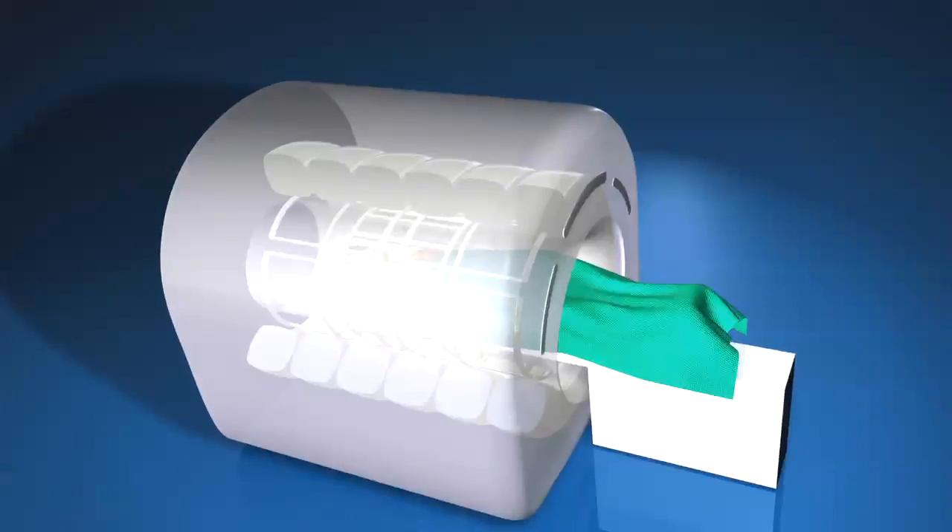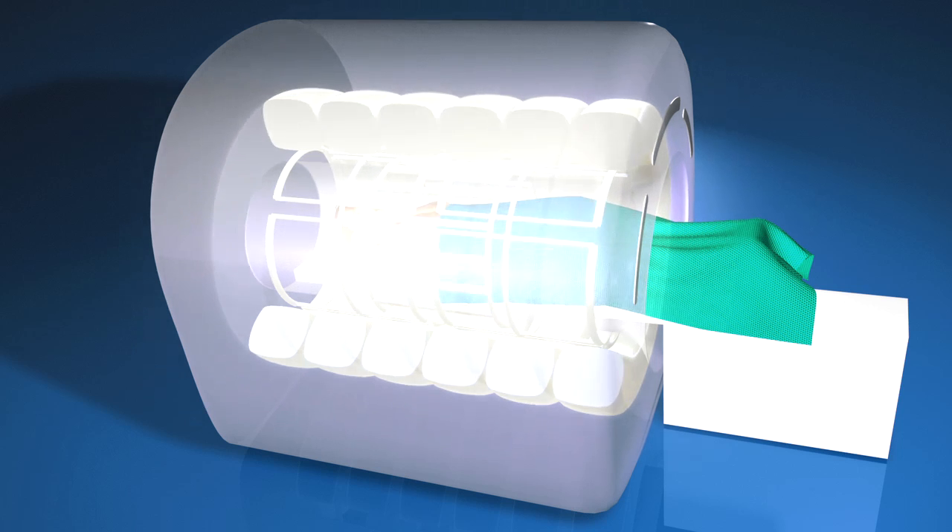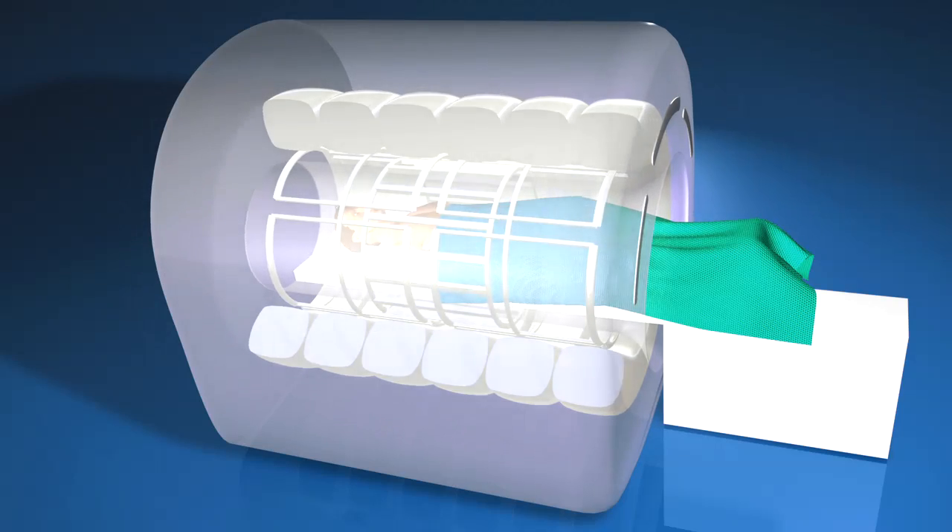Powerful fields in an MRI pose hazards for current pacing systems, including static magnetic fields. Static and gradient fields may cause relatively benign effects on the pacemaker, such as vibration, or more serious effects, such as reed switch polarization, causing the reed switch to become stuck in an open or closed position.